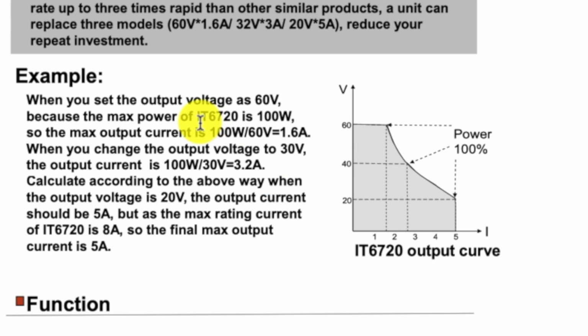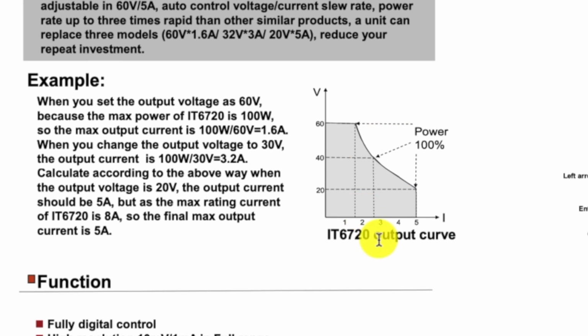So I have the IT6721, which goes up to 8 amps. So the curve for mine would go out here to 8 amps and just be a little different. But this is what I call the power curve. Some power supplies, you can't get full voltage and full current out. So you have to also know what the wattage of the power supply is. So this is a great example.